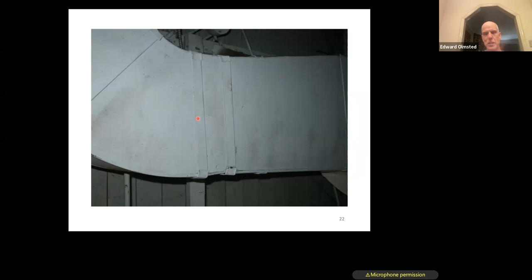So you get this situation we call humidity mold. This is actually a picture from this past summer, in a CUNY building. What happens is, say throughout COVID—or maybe not even COVID—if you're air conditioning a building and you're either short cycling, as I mentioned before, or you have no occupants and no heat load, you can overcool the building and the system won't dehumidify. It's just overcapacity. They designed the system for 1,000 people in the building, but you really only have 50, so the system never stays on long enough, and you end up with high humidity.